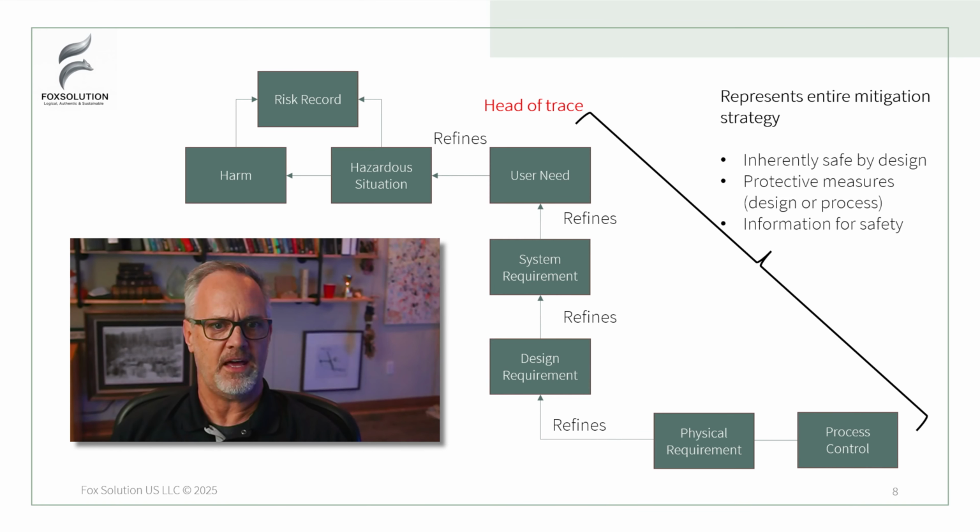We have a harm that is patient infection, and we have a hazardous situation that a non-sterile device introduces bacteria to the patient. We need that hazardous situation to be at a high level because the definition of a hazardous situation is the mechanism by which a hazard is exposed to a user. So we need to understand what's happening at the user level for us to understand what the hazardous situation is. Now, what a lot of people will do is they'll have a discussion about errors, and errors happen in the design. And then what they do is they attach it directly to the harm so that they understand what the severity is. What we want to do is have a systematic approach.